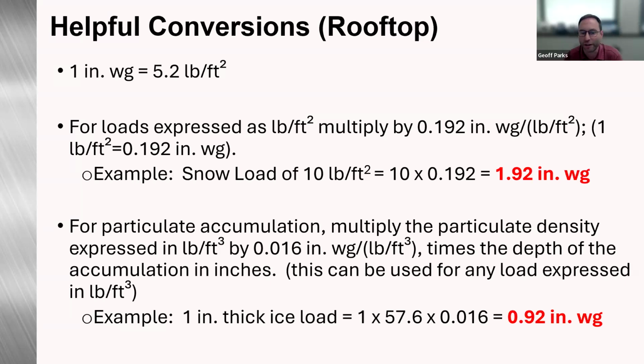So if any particulate accumulation, in pounds per cubic foot, you would take 0.016 inch water gauge, multiply that by the depth of the accumulation in inches, and this can be used for any load expressed in pounds per cubic foot, insulation and so forth. But for this example, I'm showing 1-inch thick ice, so that would be 1 times 57.6 times 0.016, and that's 0.92 inches of water gauge. This will hopefully all make sense on the next slide.